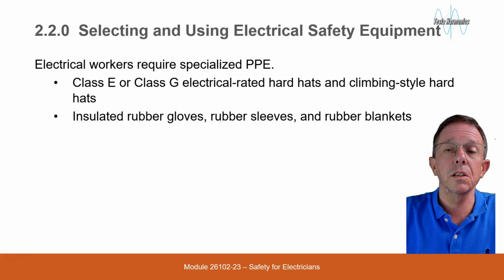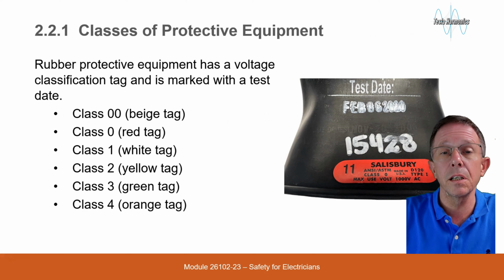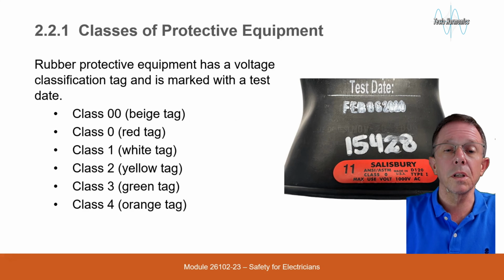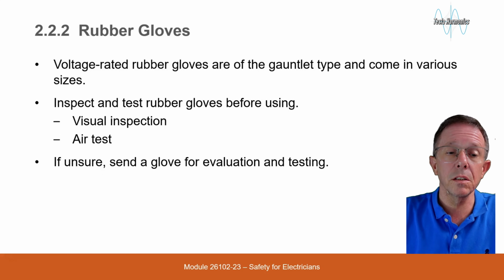Selecting and using electrical safety equipment. Electrical workers require specialized PPE: Class E or Class G electrically rated hard hats and climbing style hard hats. Insulated rubber gloves, rubber sleeves, and rubber blankets. Rubber protective equipment has a voltage classification tag and is marked with a test date. Class 00 has a beige tag, Class 0 has a red, Class 1 has a white tag, Class 2 has a yellow tag, Class 3 has a green tag, and Class 4 has an orange tag.